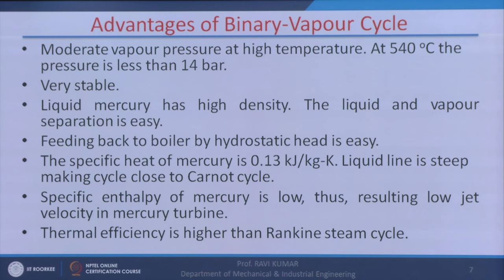In addition to this, liquid mercury has high density, and therefore the separation of liquid and vapor in the case of mercury is easier. The mercury can be fed to the boiler by hydrostatic head only. The pump is not required in this case. If you want to feed mercury into the boiler, it can be fed through hydrostatic pressure only, because the density of the mercury is very high. So, the pump can be eliminated.